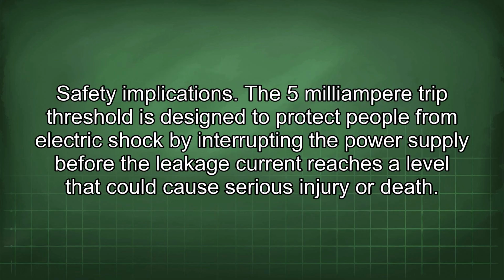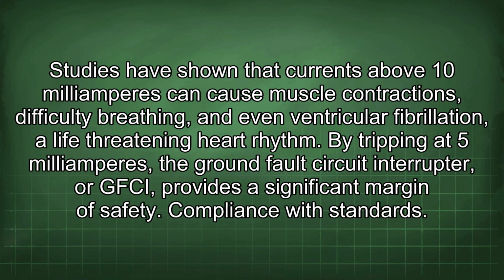Safety implications. The 5 mA trip threshold is designed to protect people from electric shock by interrupting the power supply before the leakage current reaches a level that could cause serious injury or death. Studies have shown that currents above 10 mA can cause muscle contractions, difficulty breathing, and even ventricular fibrillation, a life-threatening heart rhythm. By tripping at 5 mA, the GFCI provides a significant margin of safety.